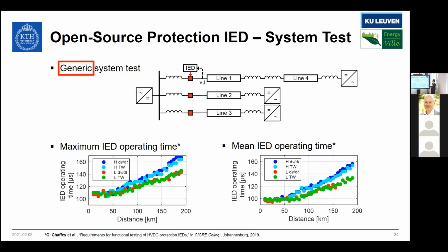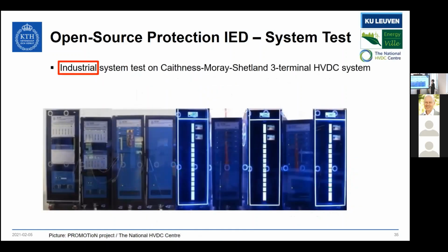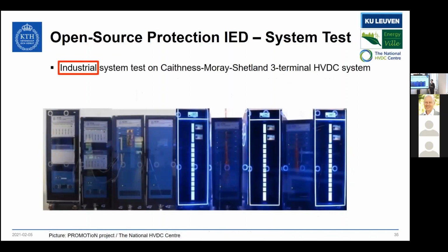And this is a generic test system, but the next step then is to go to an industrial test system. And here we're back at the Caithness-Moray-Shetland 3-terminal system. And what you can see here are the simulators in the National HVDC Centre in Scotland. So that's an industrial test centre, and their task is to de-risk ongoing and future HVDC projects in Scotland. And they have, as you can see, a very large computation power and also access to industrial grade control and protection systems.